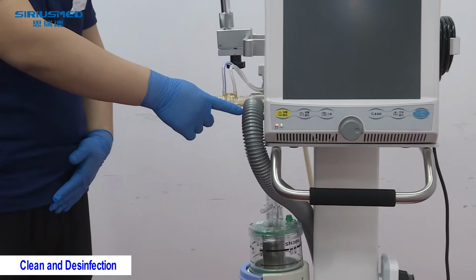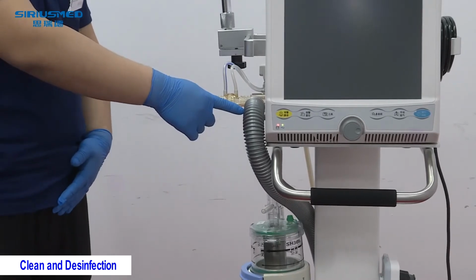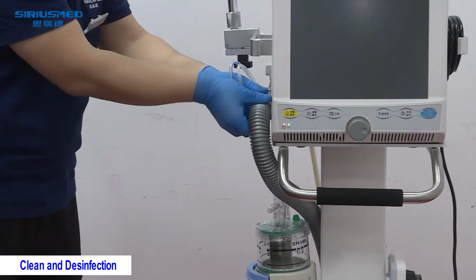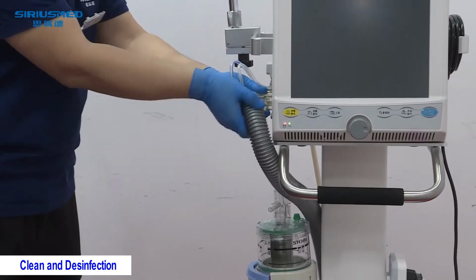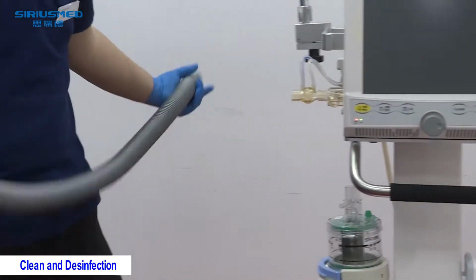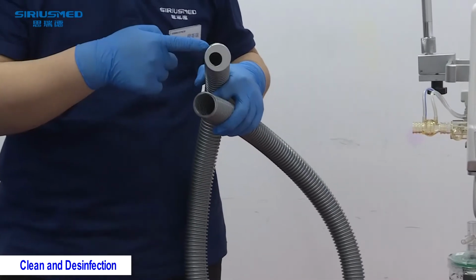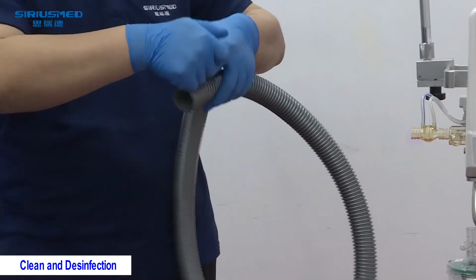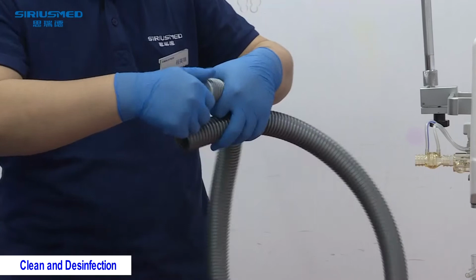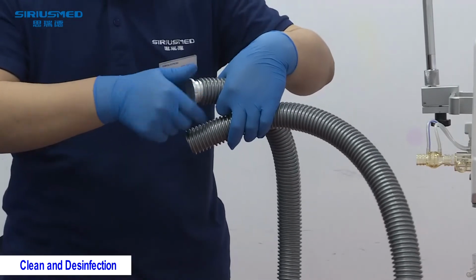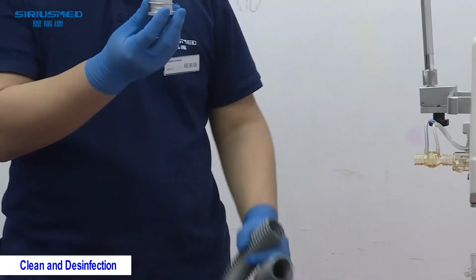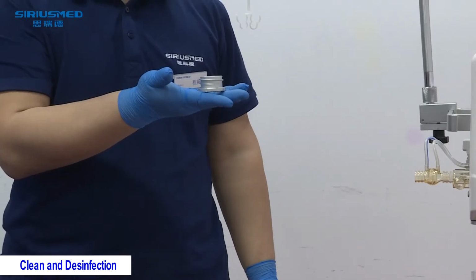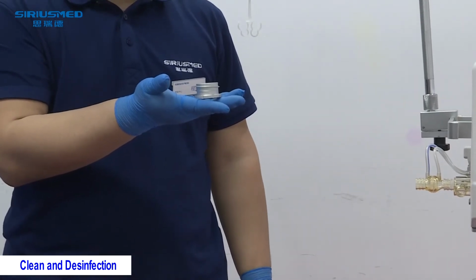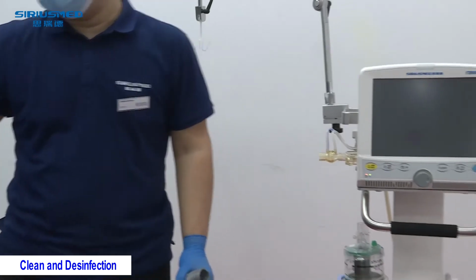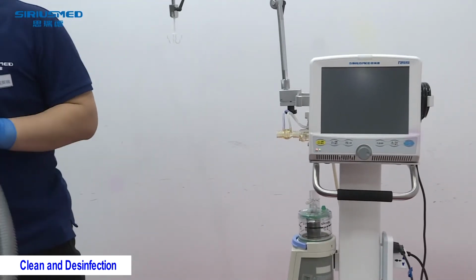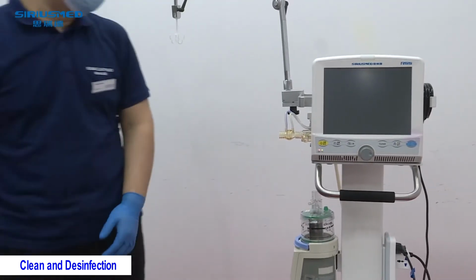Okay, the next disposable part is the exhaust hose. This hose contains two parts, the metal connector and also the exhaust tube. The tube is disposable. We need to take off the connector by turning it clockwise. And this one we can use for different patients after the disinfection.